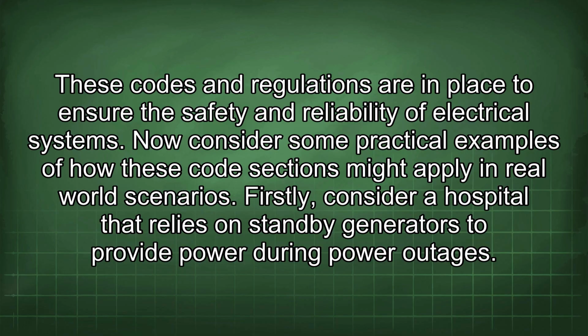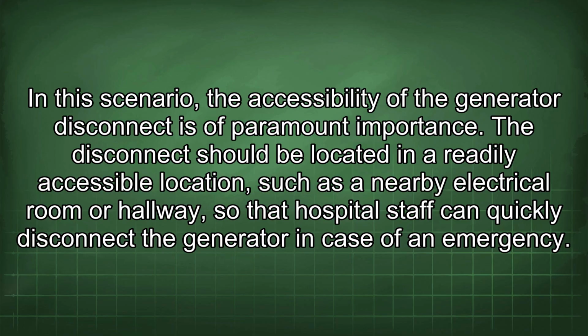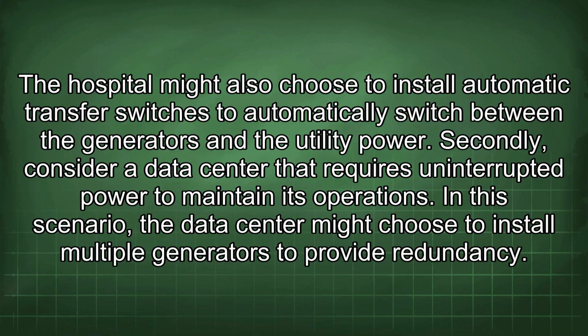Now consider some practical examples of how these code sections might apply in real-world scenarios. Firstly, consider a hospital that relies on standby generators to provide power during power outages. In this scenario, the accessibility of the generator disconnect is of paramount importance. The disconnect should be located in a readily accessible location, such as a nearby electrical room or hallway, so that hospital staff can quickly disconnect the generator in case of an emergency. The hospital might also choose to install automatic transfer switches to automatically switch between the generators and the utility power.